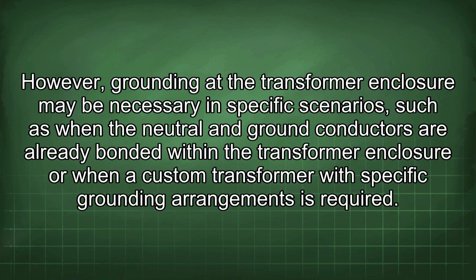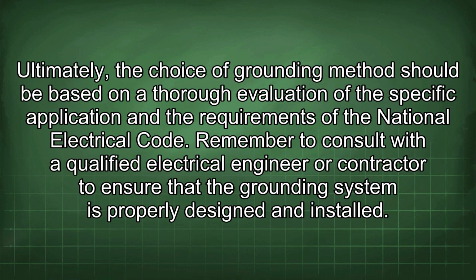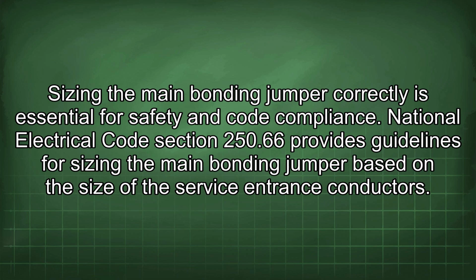However, grounding at the transformer enclosure may be necessary in specific scenarios, such as when the neutral and ground conductors are already bonded within the transformer enclosure, or when a custom transformer with specific grounding arrangements is required. Ultimately, the choice of grounding method should be based on a thorough evaluation of the specific application and the requirements of the National Electrical Code. Remember to consult with a qualified electrical engineer or contractor to ensure that the grounding system is properly designed and installed. Sizing the main bonding jumper correctly is essential for safety and code compliance.